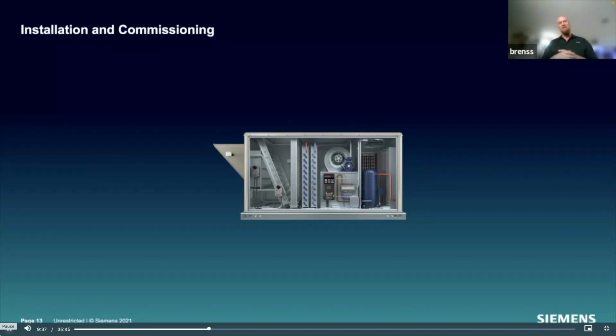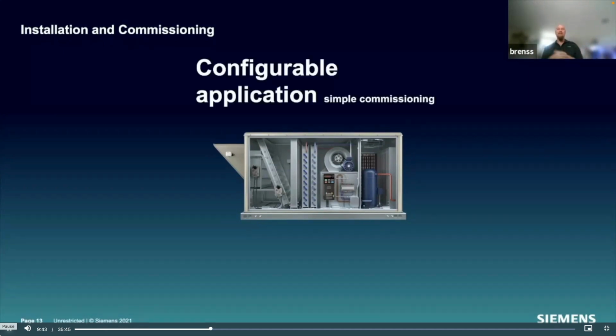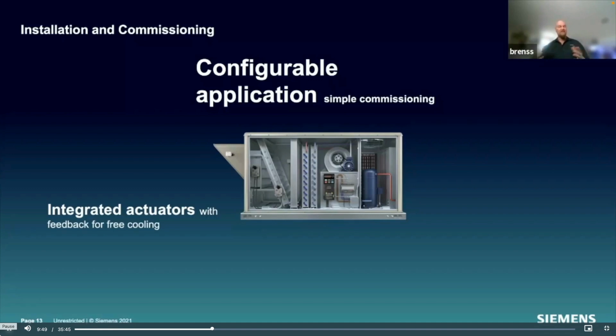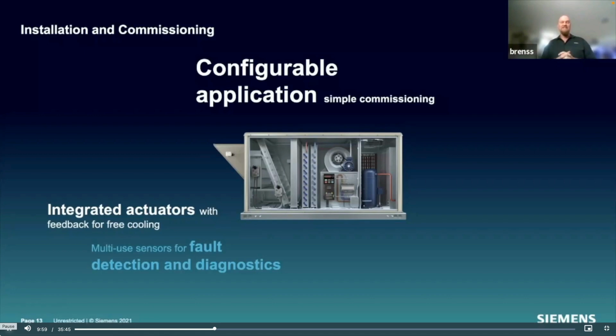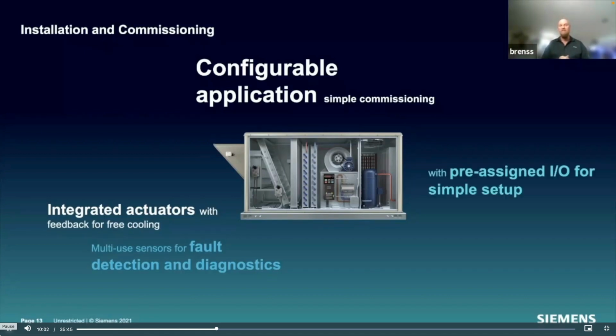Let's talk a little bit more about installation and commissioning. I've talked about some of the features and functionalities, but how do we get a configurable solution so simple like this? It all is built into the controller. You take it out of the box and it's all done for you. Integrated actuators with feedback for free cooling, all built in. Multi-use sensors for fault detection and diagnostics. There's 27 built-in alarms. They're already set for you. There's no programming needed whatsoever.